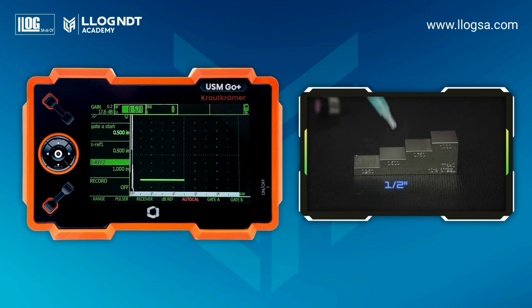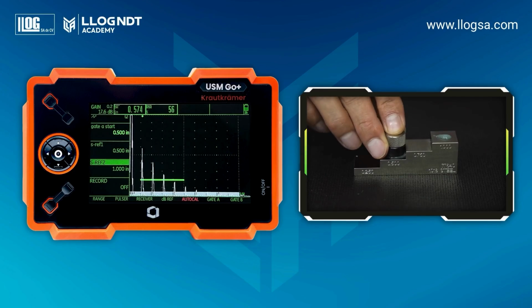Place the transducer on the step corresponding to 1/2 inch. Increase or decrease the gain until the first echo reaches approximately 80% amplitude. This is for reference only. Move the gate to the first echo. In the record function, press the right navigation key once to enable the auto calibration function. To save the first reference, press the right key again.